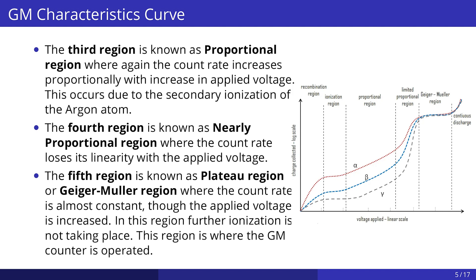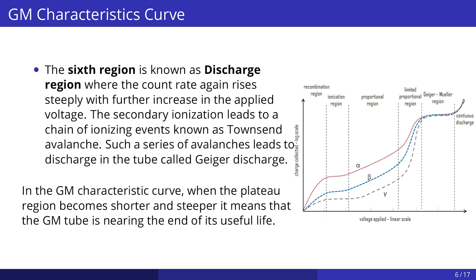The fourth region is known as the nearly proportional region, where the count rate loses its linearity with the applied voltage. The fifth region is known as the plateau region, or Geiger-Muller region, where the count rate is almost constant even though the applied voltage is increased — in this region, further ionization is not taking place, and this is where the GM counter is operated. The sixth region is known as the discharge region, where the count rate again rises steeply. The secondary ionization leads to a chain of ionizing events known as Townsend avalanche, and such a series of avalanches leads to discharge in the tube, called Geiger discharge.